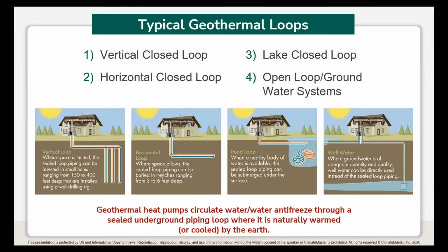We also have what we'll call a pump and dump, because you have heard of that term before, chances are good. Many municipalities are putting high restrictions on this type of ground loop, if you will. Some are making us, as an industry, put the water that we extracted from the ground and run through the piece of equipment back into the same aquifer that we took it out of. Other municipalities and DNRs are saying, no, we don't want any open loop systems in our municipality, and we must then consider some sort of ground loop.